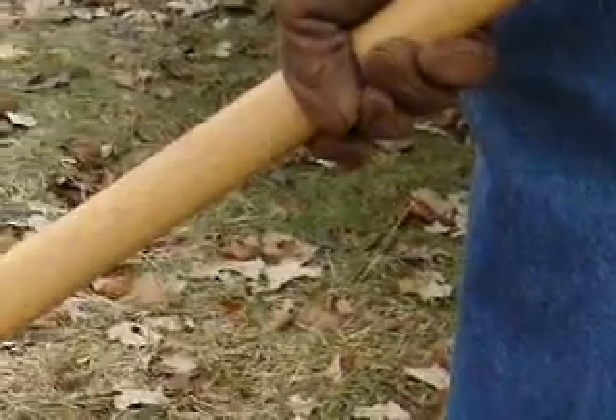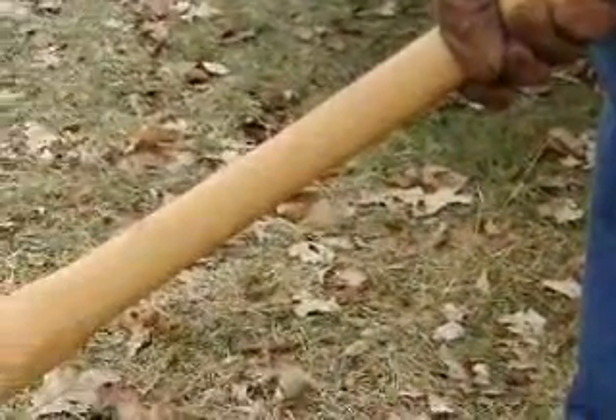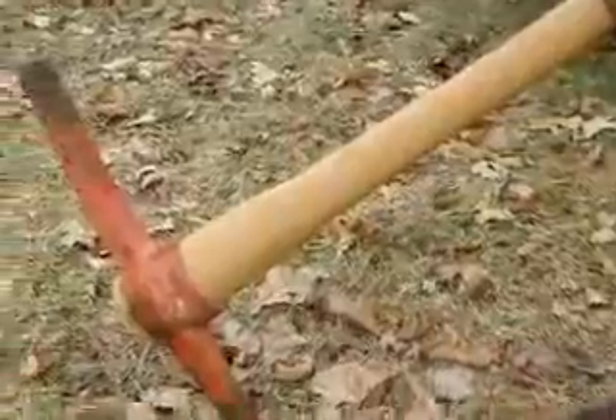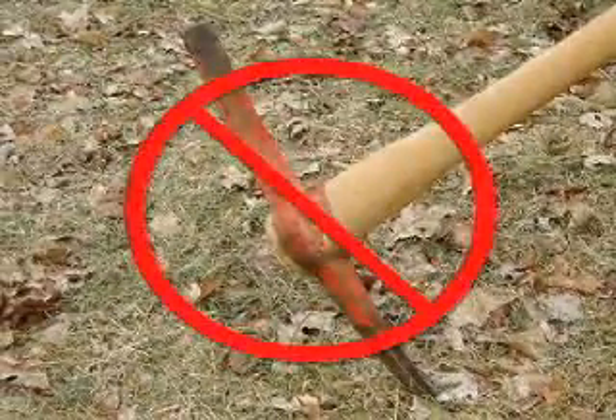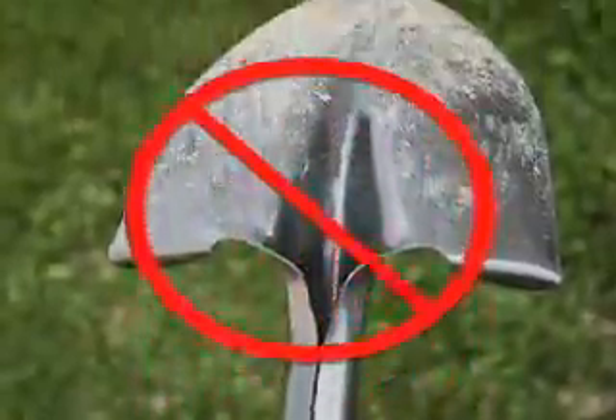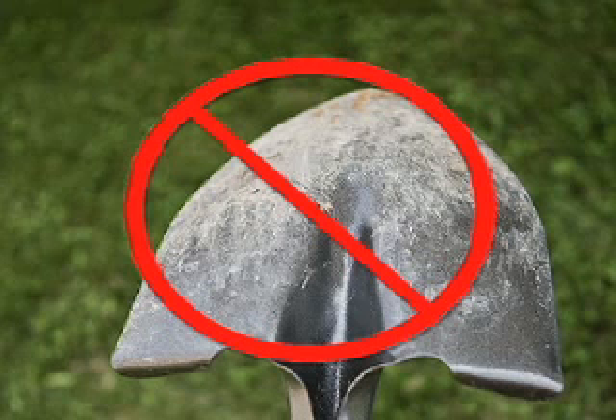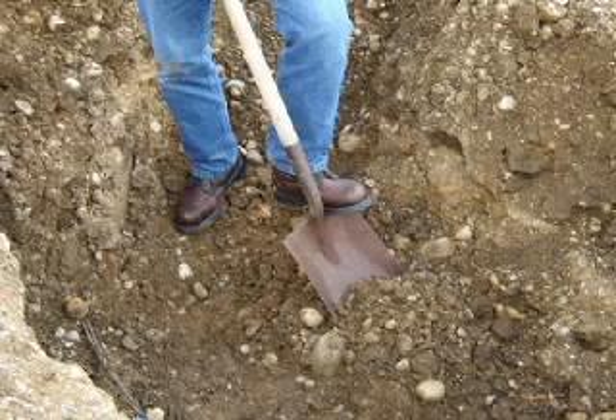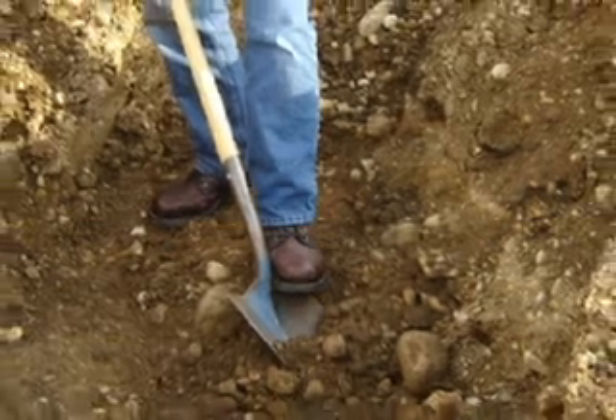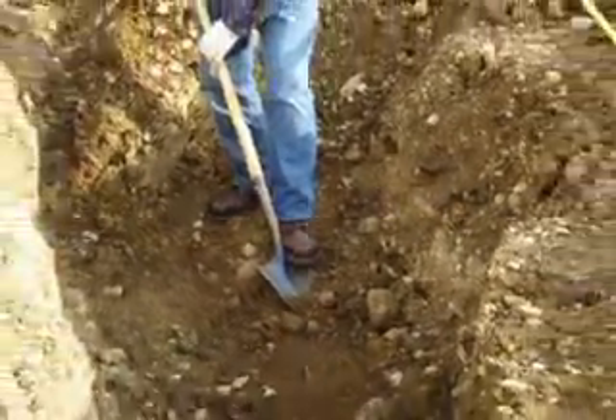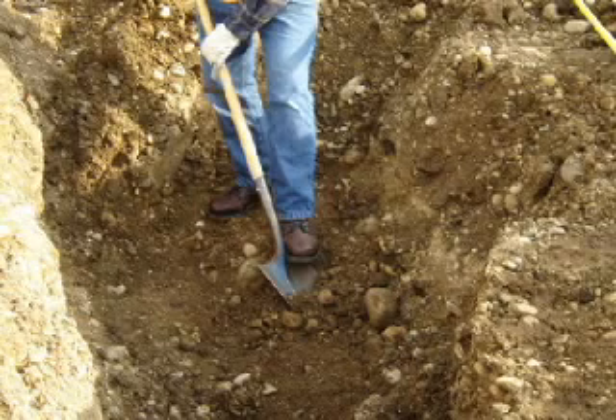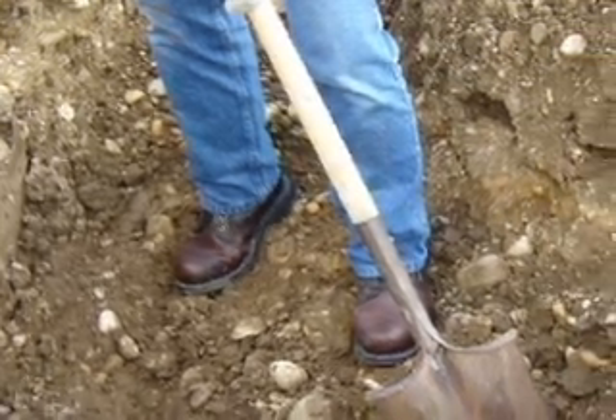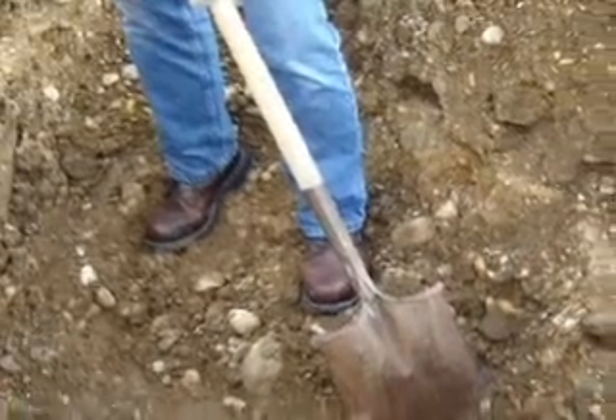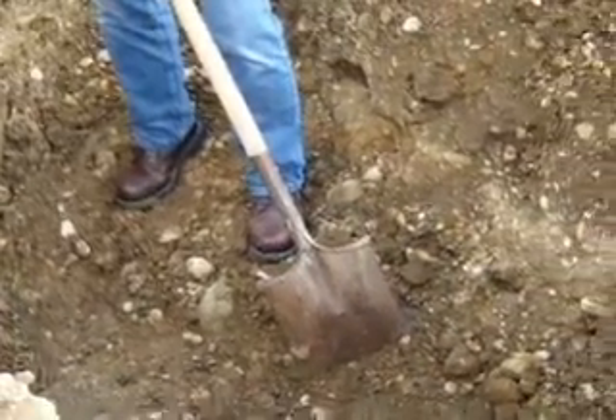When hand digging, it's important to use proper tools and techniques to safely verify the depth of an underground transmission line. Never use a pickaxe or a pointed spade, or stab at the soil or jump on the shovel with both feet. Instead, use a blunt nose shovel to loosen the soil and a regular shovel to remove it. Dig to the depth where you expect the line to be, but off to one side. Then, using a prying motion, break away soil from the side of the underground transmission line.